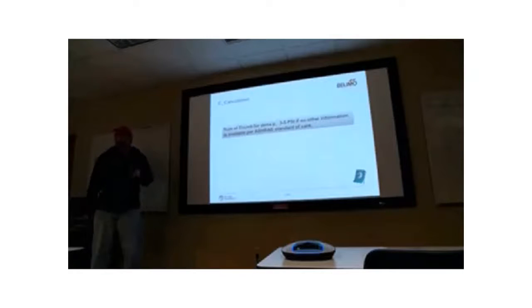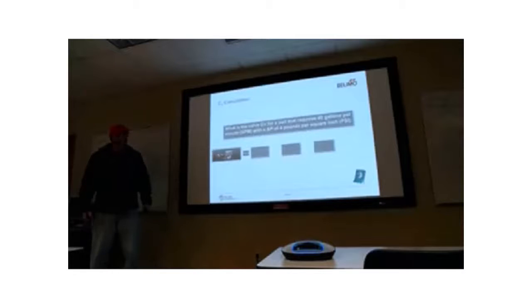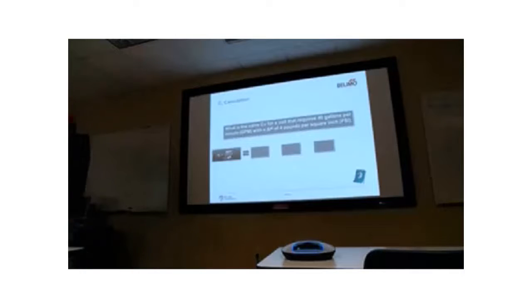Even number. The math gets really easy. It's an even number, but the math gets easy, because what's the square root of 4? 2. So you can do that one in a truck. You can be driving down the road, and the guy says, I got a 150 GPM valve. What's the CV? 75. I mean, you're a genius.